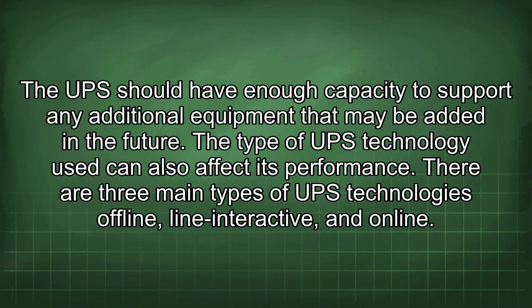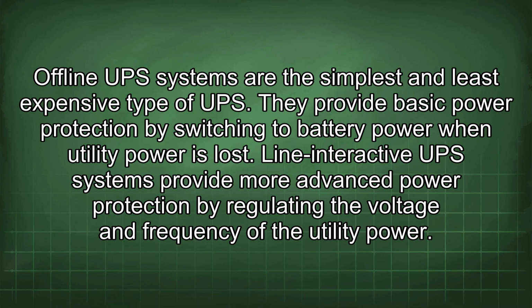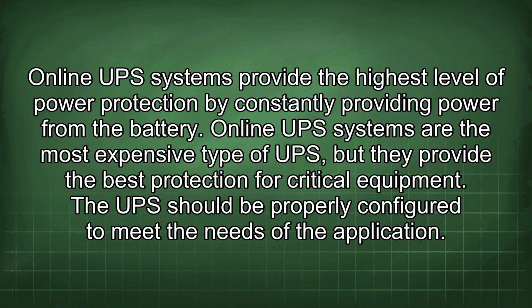The type of UPS technology used can also affect its performance. There are three main types of UPS technologies: offline, line interactive, and online. Offline UPS systems are the simplest and least expensive type of UPS. They provide basic power protection by switching to battery power when utility power is lost. Line interactive UPS systems provide more advanced power protection by regulating the voltage and frequency of the utility power. Online UPS systems provide the highest level of power protection by constantly providing power from the battery. Online UPS systems are the most expensive type of UPS, but they provide the best protection for critical equipment.